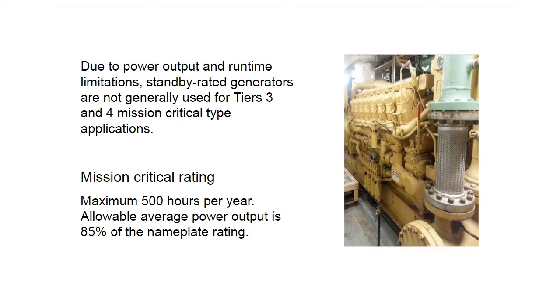Again, like I said, because of Tier 3, Tier 4, the runtime and the output a lot of times will not allow you to use the standby rating generators. We'll start looking at the prime rating. A lot of engine manufacturers now have what they call a mission critical rating. It's basically 500 hours per year, but the average becomes 85%. And this is based on the fact that these are constant loads. They're not going to swing. They're not going to go up and down. You're going to have a constant load over a certain amount of time. So they've adjusted the rating of the engine. So that's something you can look into.